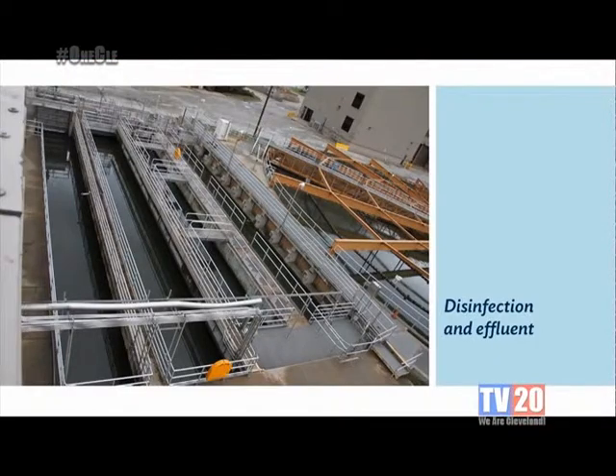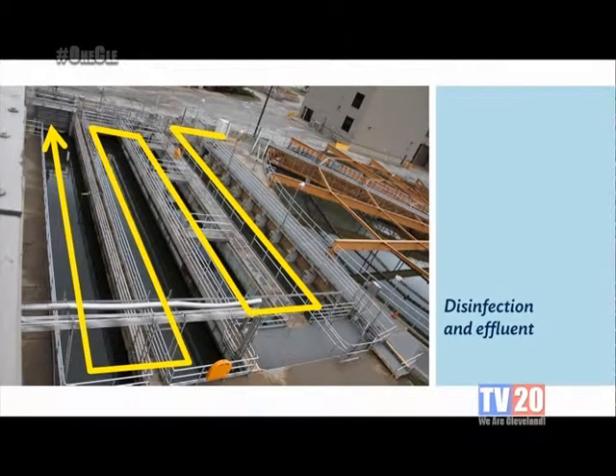So we've gotten the solids down to whatever the EPA levels are: chemical constituents, metals, organic compounds, everything. So that's secondary treatment. The very end of the process, though, in the recreation season, we need to disinfect. These tanks are disinfection tanks. Chlorine's applied at the front where the water's coming in, and it's bleach, sodium hypochlorite. And the bleach, with mixing and time, kills off microorganisms. And E.